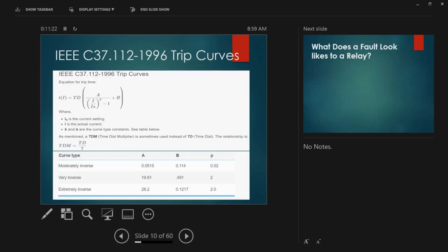The IEEE is the same. You have all the constants over here, but most of the time we're using a formulated Excel sheet. But that's where this comes from. All the constants, and you have the time dial from the relays. So those are the two. Sometimes different relays prefer different standards, but the purpose is to properly coordinate the trip of the relays. If you want this to trip first, you pick the right curve. If you want this to trip last as your last point of defense, which is the incomer, you don't want to trip the incomer first, isn't it? Because it will trip the whole production.